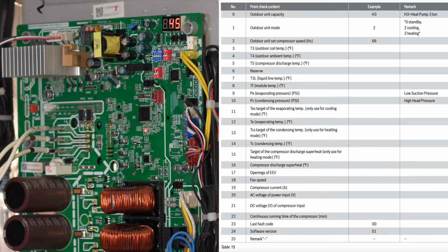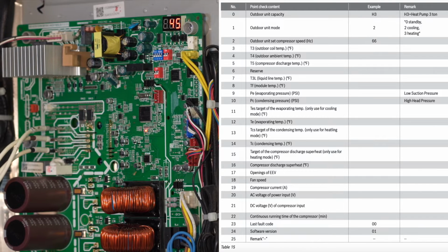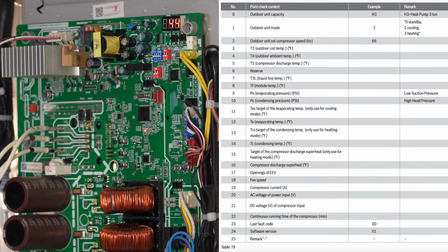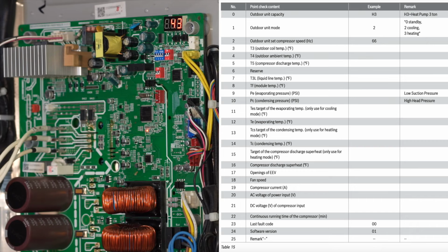Okay? I don't remember what those numbers were, but I'm going to let Ken tell us what those numbers are, what they represent, and tell us about the 3 dashes. Okay. Ken, you're on. Okay, so the 0 is actually a number when we're going through the parameters on this. So the 0 was an H2. That tells us that it was a heat pump and that it's a 2-ton. The 01 was the number 2. 0 is static or off. 2 is the cooling mode. And 3 would be your heating mode. So that tells us what mode we're in.